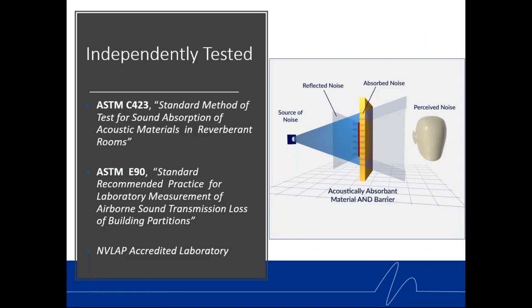All of these noise block panel products, in different configurations, are independently tested. Independent testing is extremely important to Kinetics. It's costly. You're not going to run something 100 times and take the best data. Instead, you run it once per the applicable ASTM standard: C423, the standard method of testing for sound absorption, and ASTM E90, the standard recommended practice for laboratory measurement of the sound transmission loss of building partitions. And they're all in a NVLAP accredited laboratory. What I always like is that we publish the data we get. We don't run it a bunch of times, look at the variances, and then give you only the best data to make it look super. We give you real-life data, something that acoustical consultants, architects, and engineers can really stand behind when they're using it to design their systems.